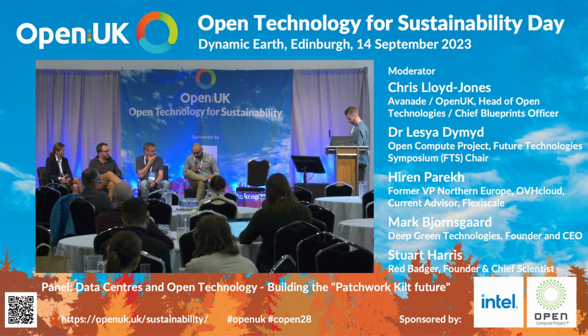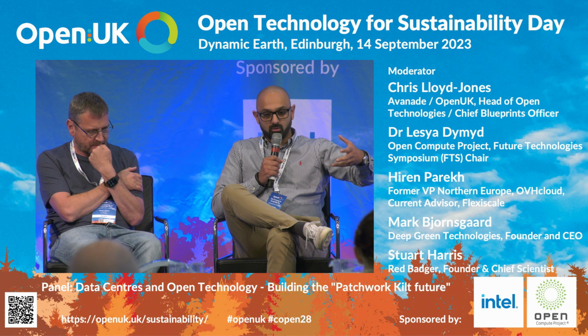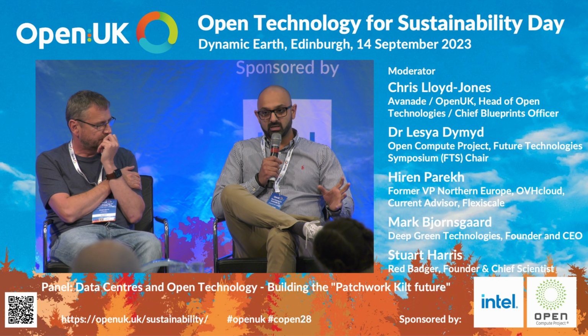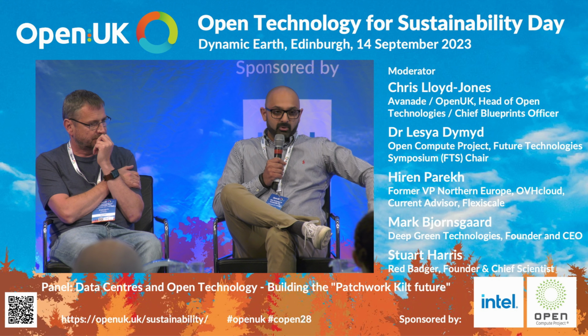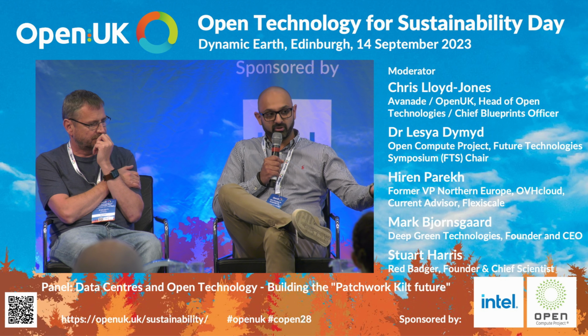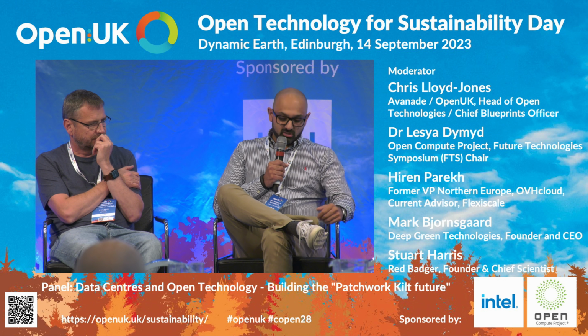Sure. So speaking first of OVH Cloud, for many years they have been using water cooling directly on the chipset itself and extracting the heat this way, which is the most energy efficient. And they've managed to create a lot of efficiencies by doing so. Not only that, but they also buy the components and produce the servers in-house. Where typical data center racks are vertical, these are horizontal, stacked 3 high, and therefore you get a higher density. They've been taking different approaches, because when you look at carbon footprint in traditional data centers, a lot of it is actually the plastic involved in the manufacturing of data centers, not just the operation. Building those more open servers enabled them to gain those efficiencies, if you like.